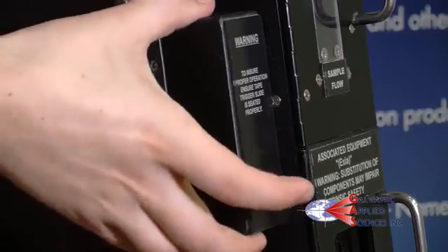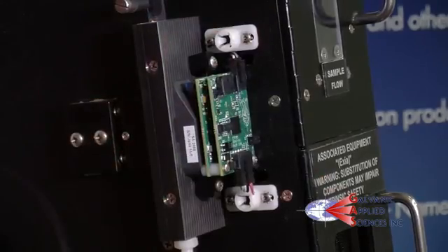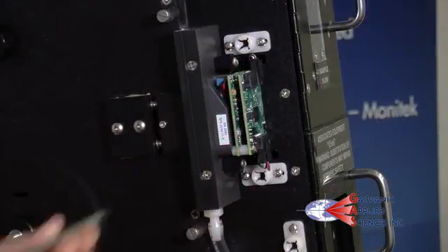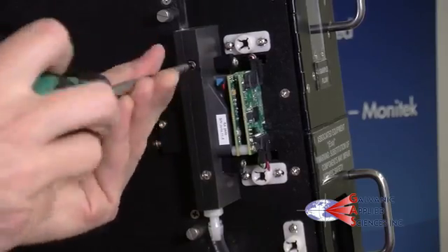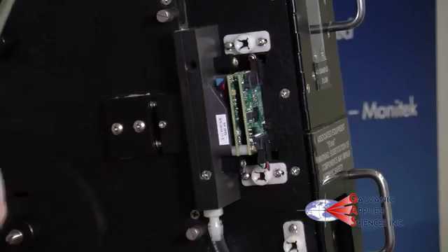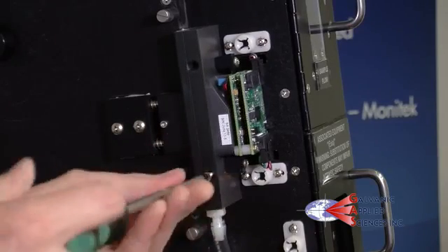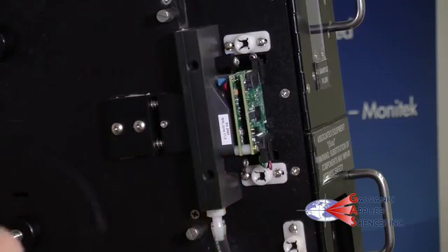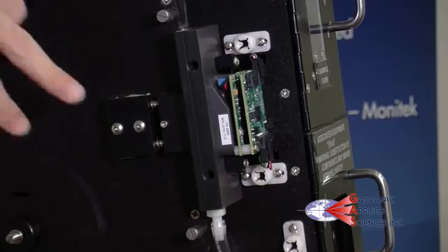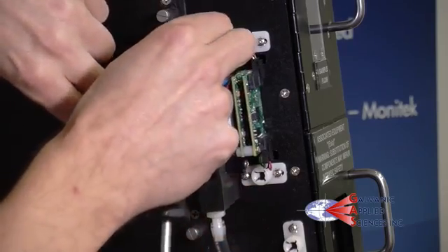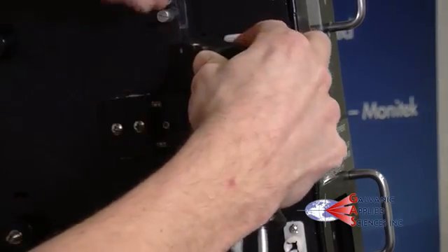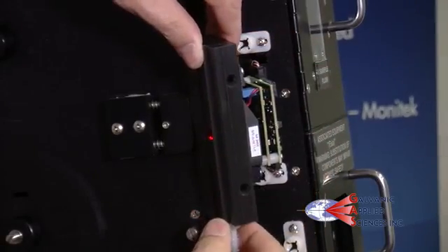Remove the sensor dust cover. Remove the two screws that hold the sample chamber in place. To pull out the sample chamber, pull back the compression head and twist to expose the sample chamber opening.